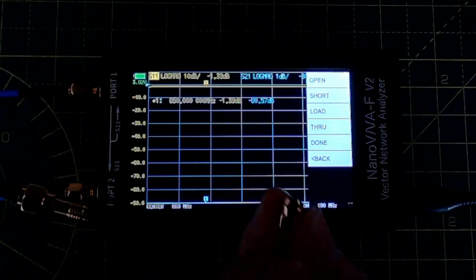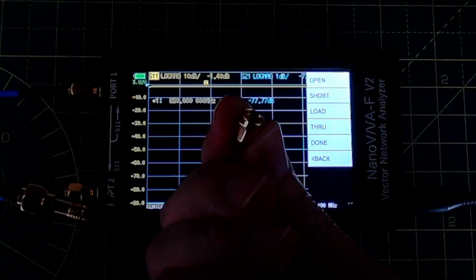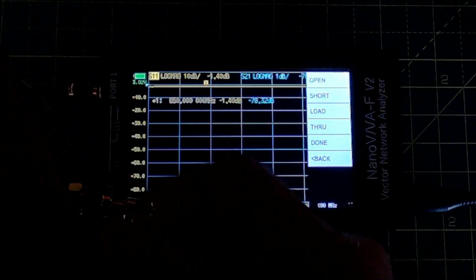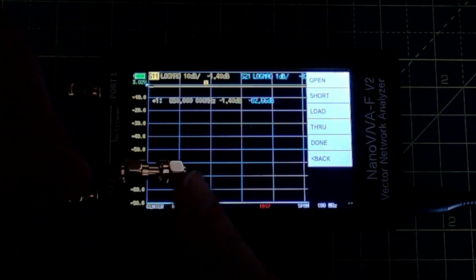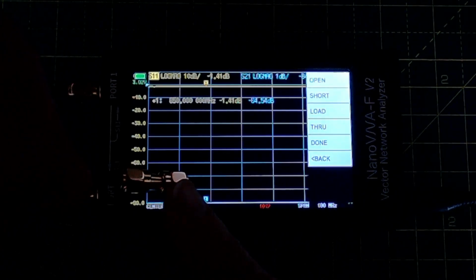You have to make sure it's the right one. This is a tiny SMA plug which has nothing inside, there's no pin, so it's an open circuit. So you put that on the end of the cable. You don't put it directly on the device, because you want to calibrate this device for what appears at the end of the cable you're going to be using when you make the measurements.